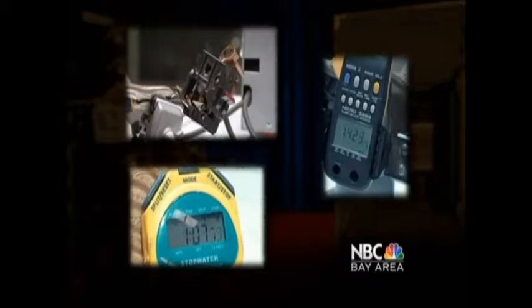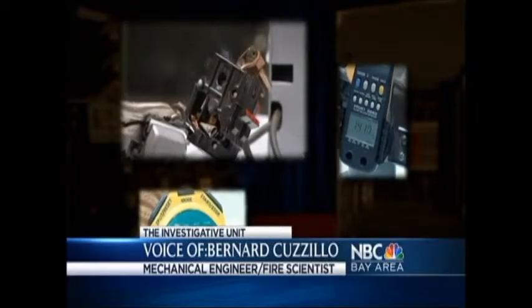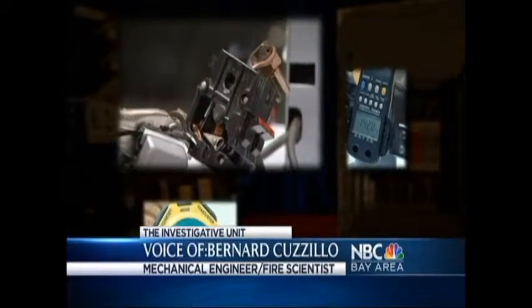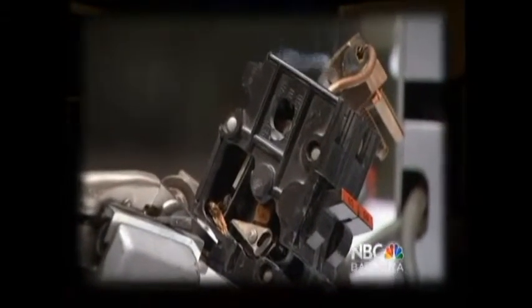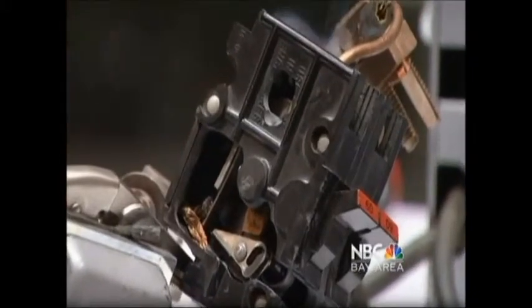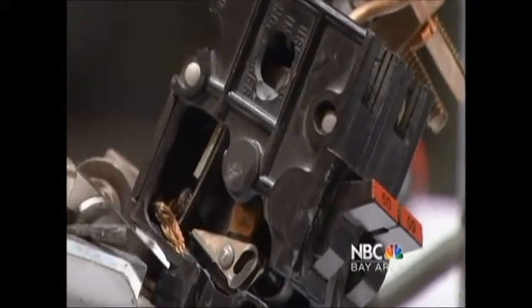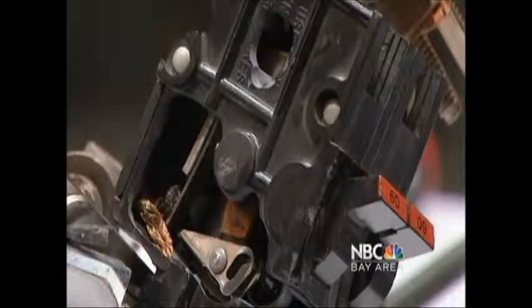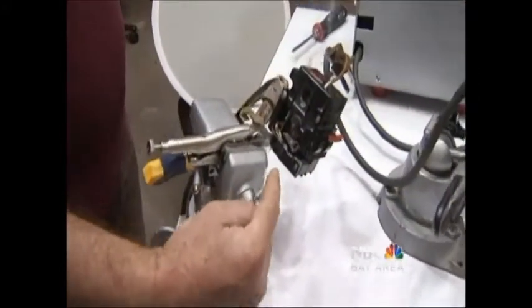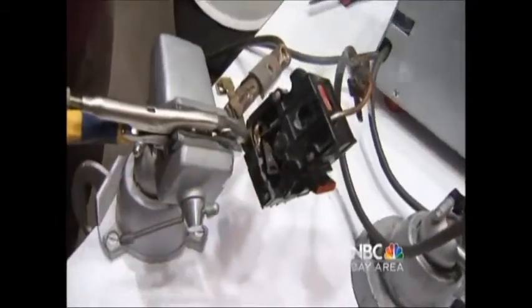That means it should trip in less than 2 minutes. We're at a minute and 10 seconds now, and there's smoke coming out of the breaker. There's a definite smoke coming out. The lab cut away some of the plastic siding so you can have a closer look, an aesthetic change that experts say will not alter the functionality of the breaker. We're almost 4 minutes in, it's smoking, and it hasn't tripped. Why not? Because the mechanical mechanism that is supposed to be tripping the breaker is stuck.